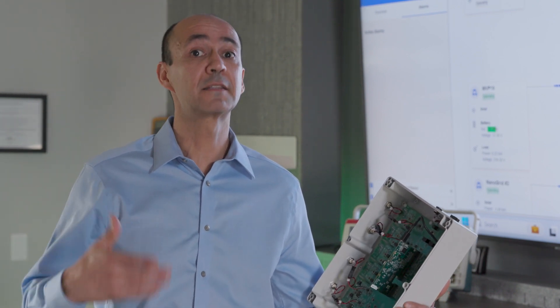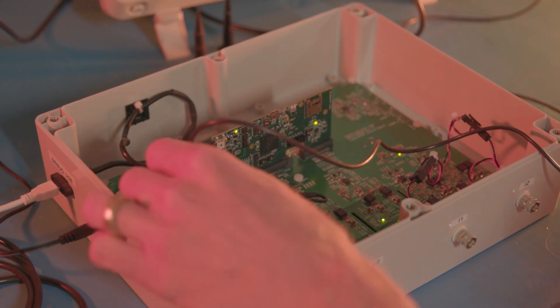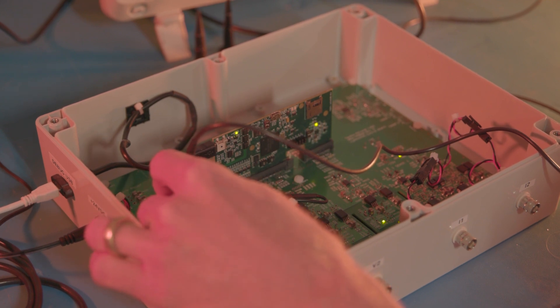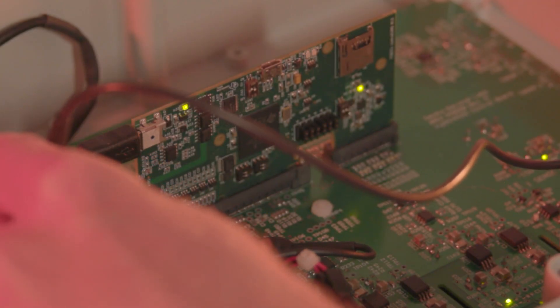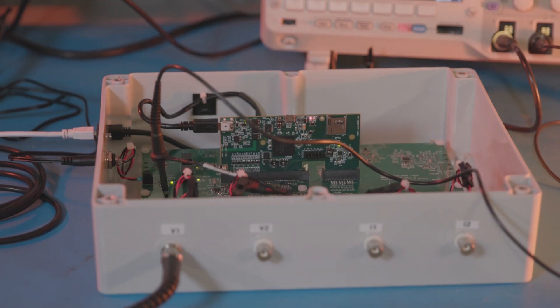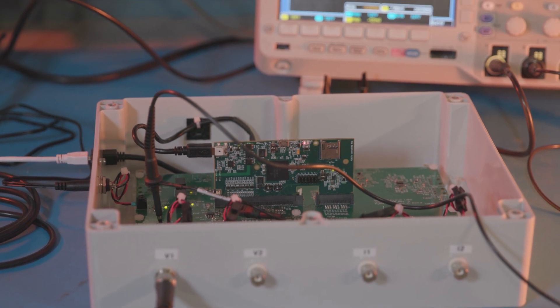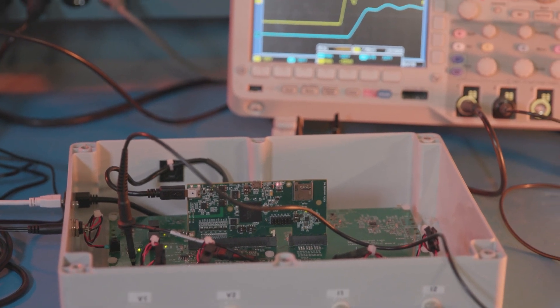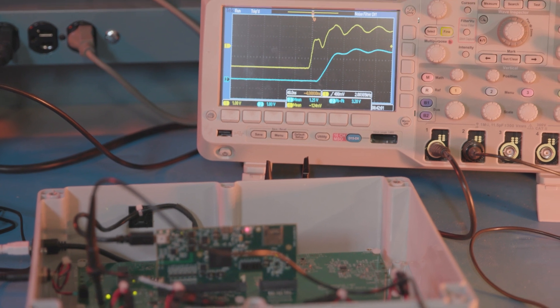The relay's microcontroller is placed on a custom printed circuit board that interfaces between commercially available voltage and current sensors and our custom hardware implementation. We have designed analog signal processing circuitry prior to the microcontroller's analog-to-digital converter inputs that provides optimal signal-to-noise ratio and signal integrity for the fault's measured traveling wave.